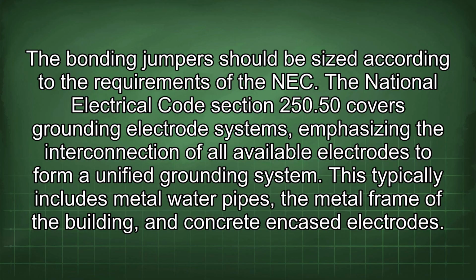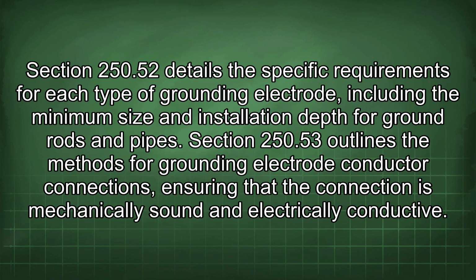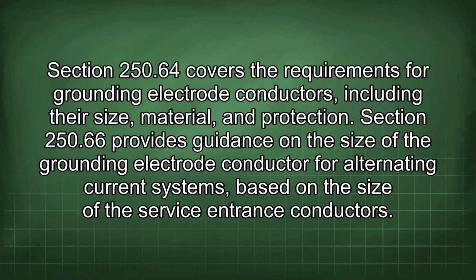The National Electrical Code Section 250.50 covers grounding electrode systems, emphasizing the interconnection of all available electrodes to form a unified grounding system. This typically includes metal water pipes, the metal frame of the building, and concrete encased electrodes. Section 250.52 details the specific requirements for each type of grounding electrode, including the minimum size and installation depth for ground rods and pipes. Section 250.53 outlines the methods for grounding electrode conductor connections, ensuring that the connection is mechanically sound and electrically conductive. Section 250.64 covers the requirements for grounding electrode conductors, including their size, material, and protection.